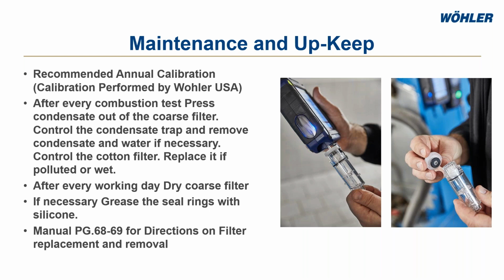We recommend too that if you have an 8550 and you have the coarse filter, that you press out the condensation and get any water out of it, and then you empty the water trap out if you notice that it fills up with water.